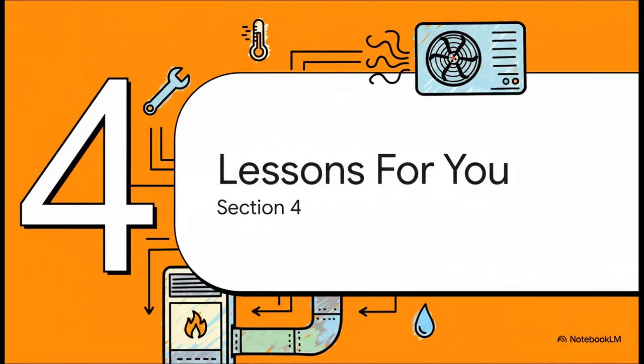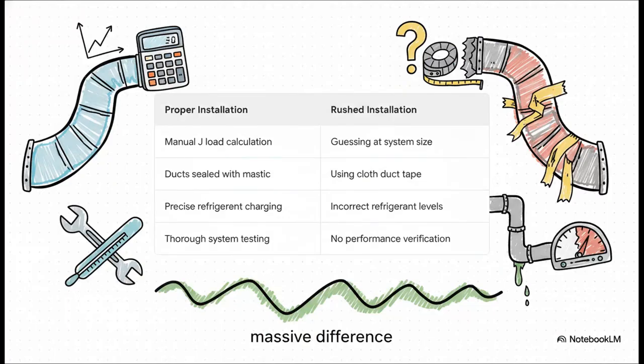So we've seen the HVAC battlegrounds in Friendswood. What can we all learn from this? What are the big takeaways for every homeowner? First and foremost, the quality of the installation is every bit as important as the quality of the machine itself. A proper install involves careful calculations, sealing ducts with durable mastic, and precise system testing. A rush job is all about guesswork, using cheap cloth tape that's just going to fail in the heat, and zero performance verification. The difference is absolutely massive.